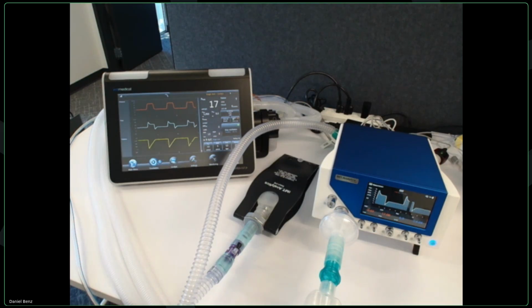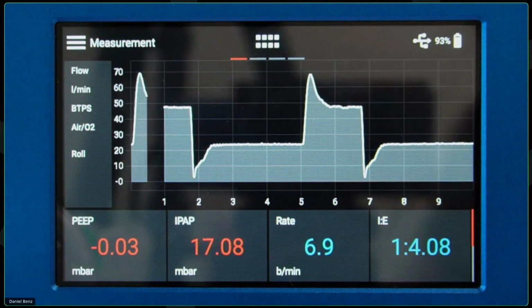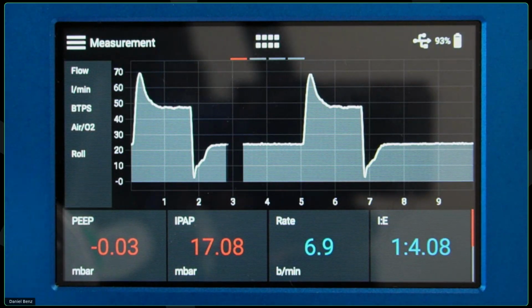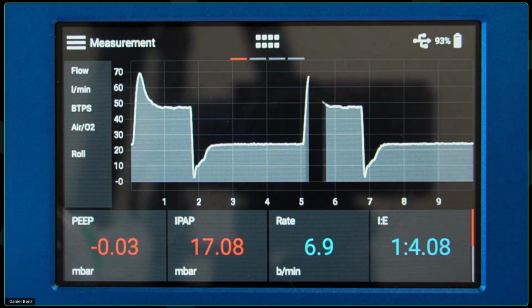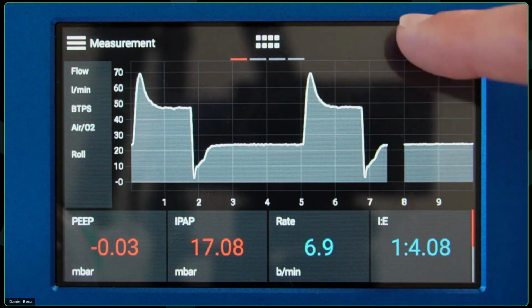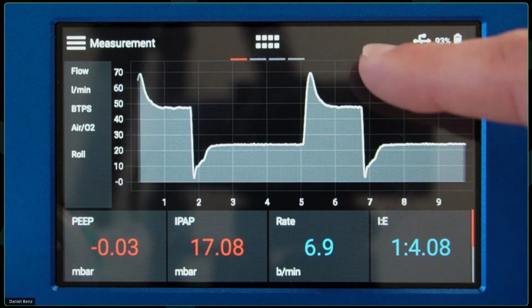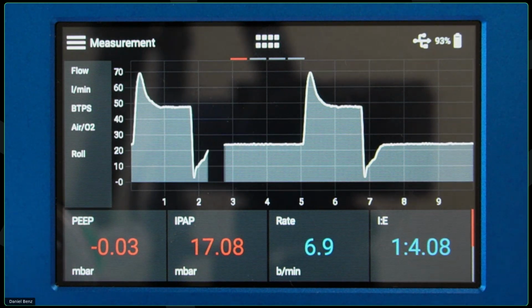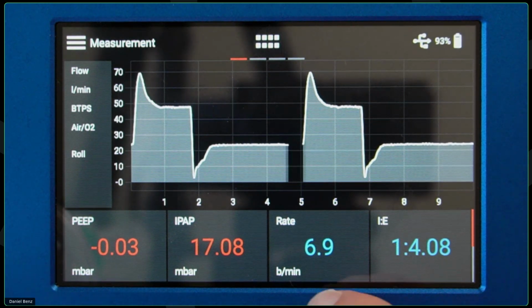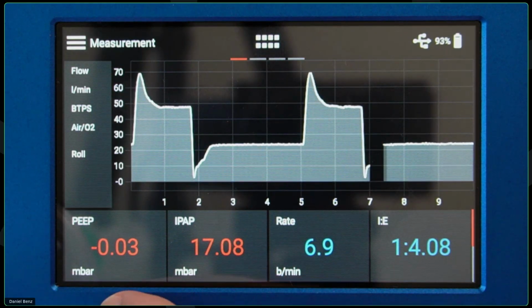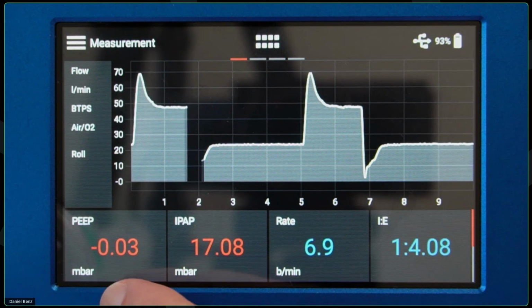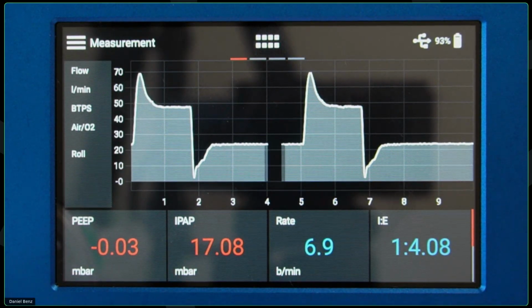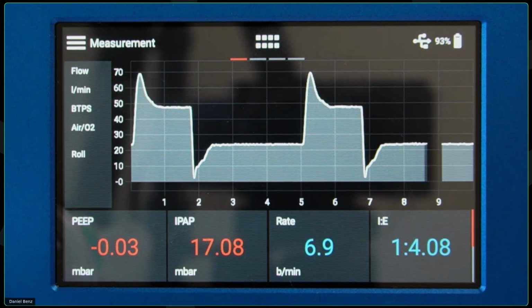So if we have a look at our FlowAnalyser screen again, you will see that now there is no negative flow through the FlowAnalyser anymore. And you can see there is no triggering. Up here, earlier we saw this T flashing up. That's no longer happening. And also my rate is set to 12, and my IPAP and EPAP is like 17 and 5 here. So you can see these measurements are no longer accurate. The reason is because the device is now not triggering.